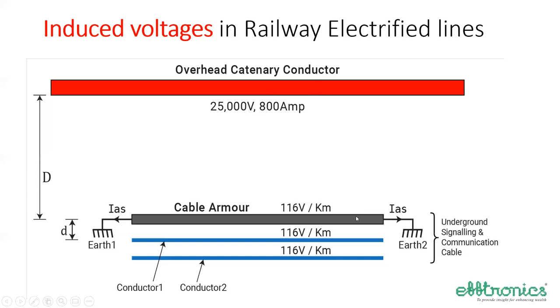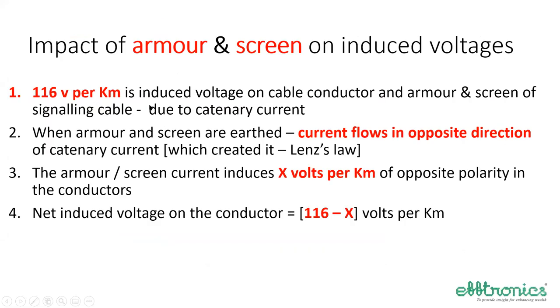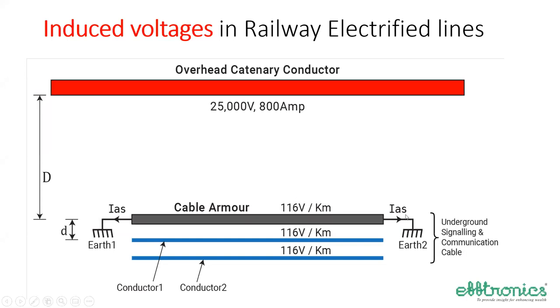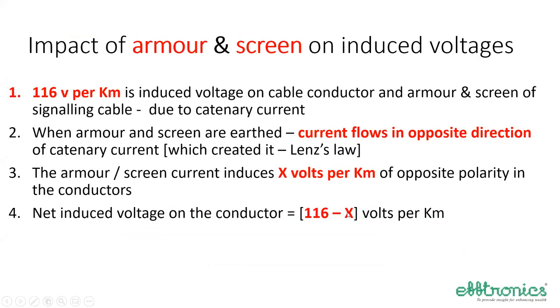This may be a few milliamperes, but it makes a big difference because the distance between the overhead catenary and the conductor is very high compared to the distance between the armor and the conductor. So in effect, if the cable armor is not earthed and we don't allow this screen current to flow, then the effect on reduction of the induced voltage is not much. So if 116 volts per kilometer is the induced voltage, and if X volts per kilometer is induced because of this current, IAS, then 116 minus X will be the resultant, the net induced voltage on the conductor.